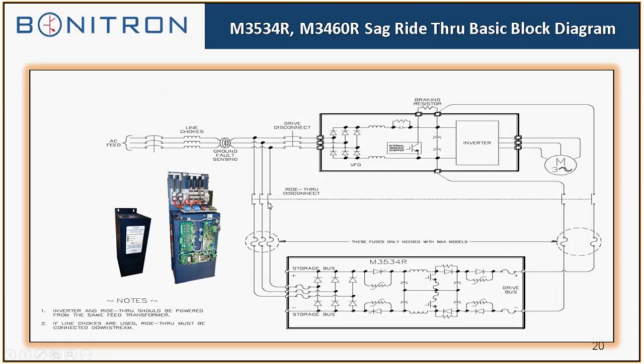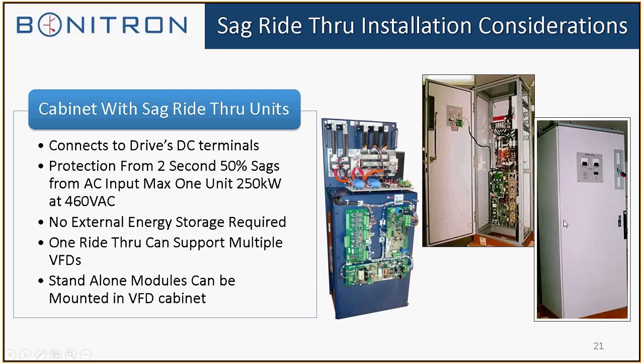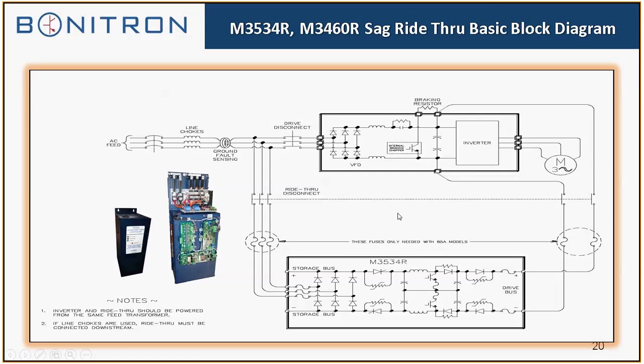As you can see, it's got AC line contacts and DC bus contacts. It's fused at the AC line and the DC bus to protect the ride-through, and protect the drive from the ride-through if there's a problem with the ride-through. Usually, when we have issues with installations, we find that it's either connectivity, or it wasn't specified correctly, or maybe it was the wrong kind of ride-through for that particular application. Maybe the utility power events are longer than what the customer anticipated, so the ride-through will time out at 2 seconds. These are designed for that, so there's not any component damage or they don't overheat. So it's a 1% duty cycle also.